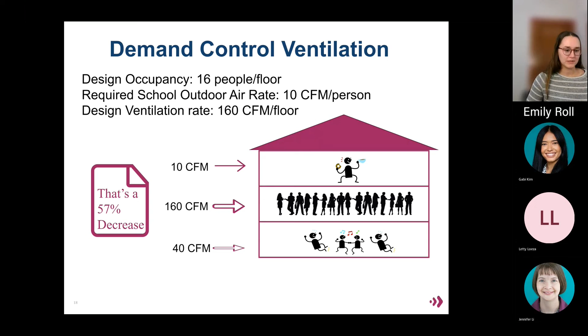Demand control ventilation reduces the outdoor air amounts based on the current or actual occupancy. When the outdoor air is reduced, there's less air and heat to heat or cool, reducing the energy consumption. In this example, demand control ventilation reduced outdoor air supplied by 57% while still providing the ventilation needed for all occupants.